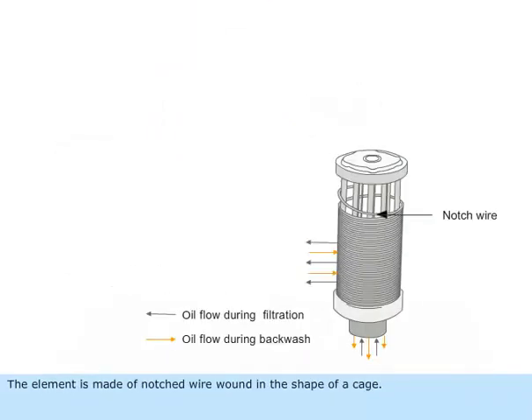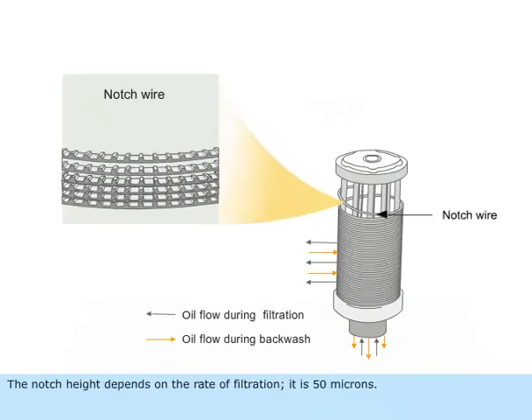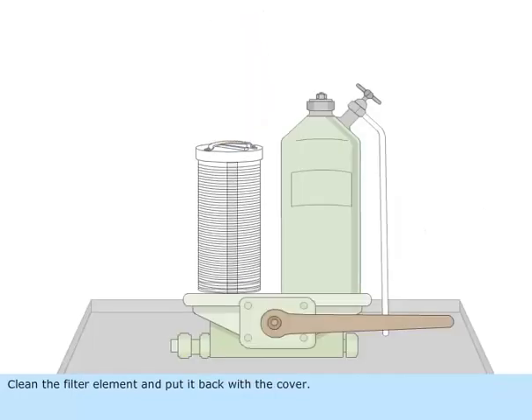The element is made of notched wire wound in the shape of a cage. The notch height depends on the rate of filtration. It is 50 microns. Clean the filter element and put it back with the cover.